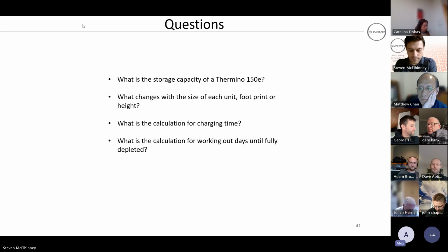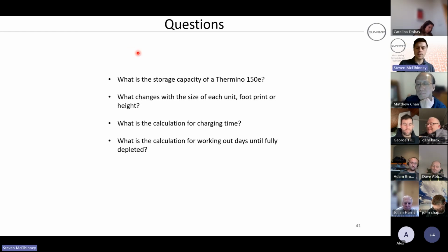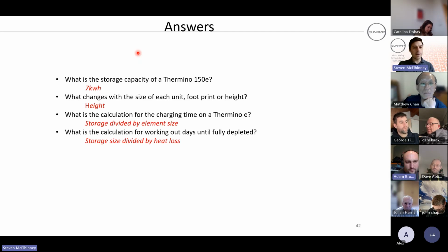What's the calculation for charging time? Power times kilowatt hours. Anyone else? Capacity divided by kilowatt hours. Kilowatt hours divided by power of the element. Yes, that's the one. So the kilowatt hours capacity divided by the element size, basically. So what's the calculation for working out days until fully depleted? Is that storage capacity divided by heat loss rate? Yeah, spot on. Absolutely spot on. Yeah, divided by the element size. Excellent. Good stuff.